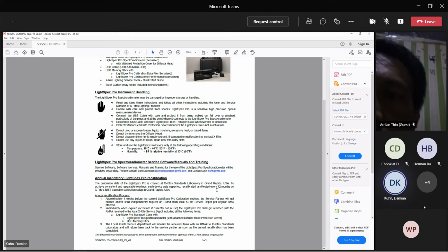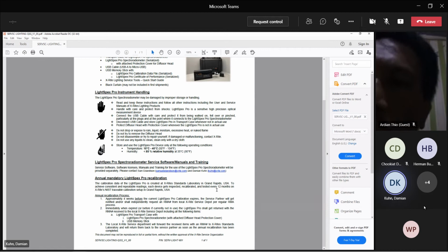And on that memory stick, you would then find the new calibration file and the new calibration certificate. So one big difference for you is that, because the new instrument is way more stable than the old one, we were able to extend the recalibration interval from 6 to 12 months. So the new instrument only requires to get returned to us on an annual basis and no longer twice a year.